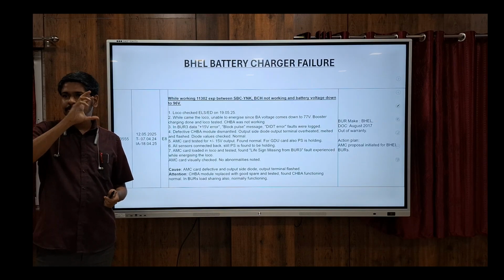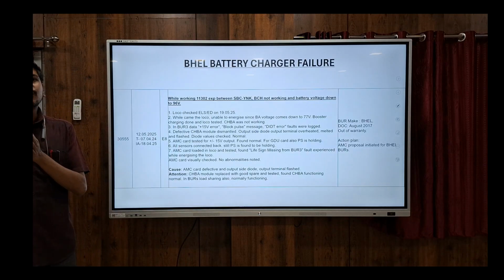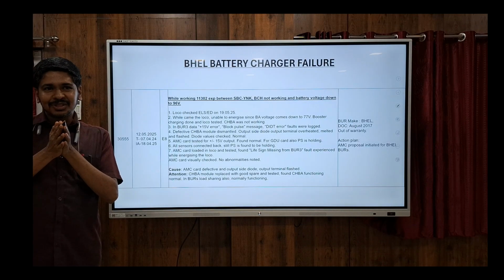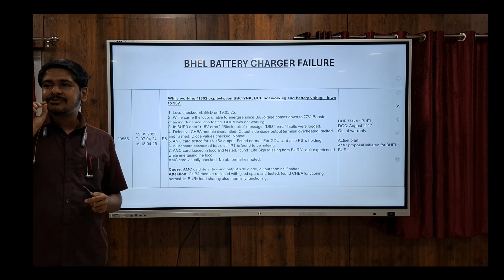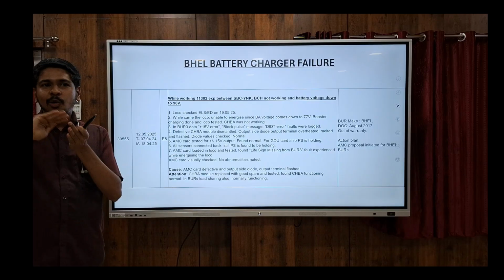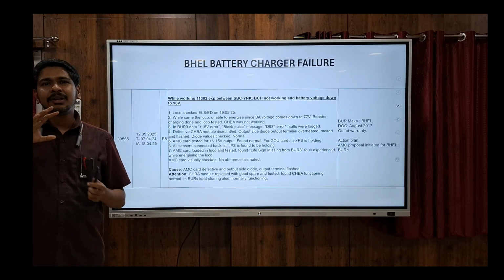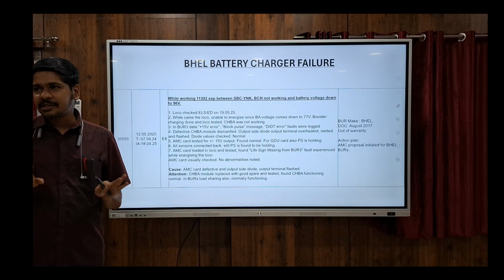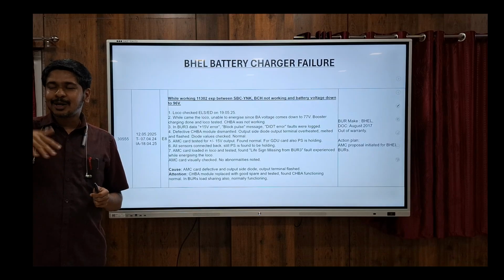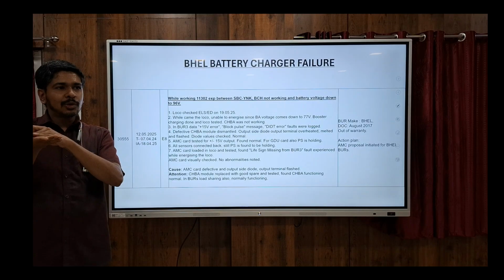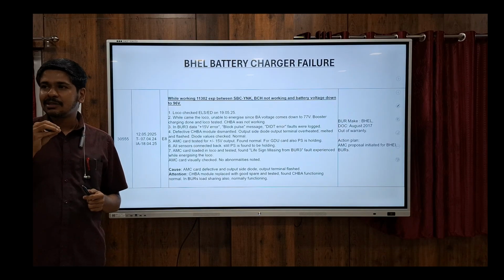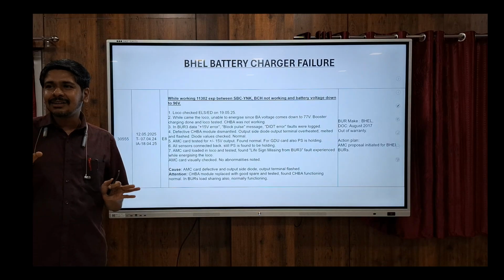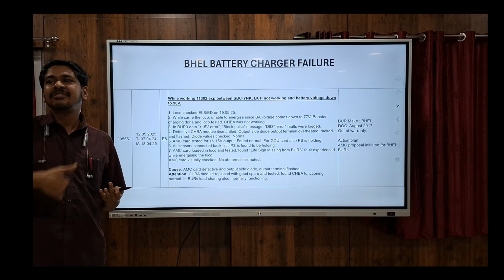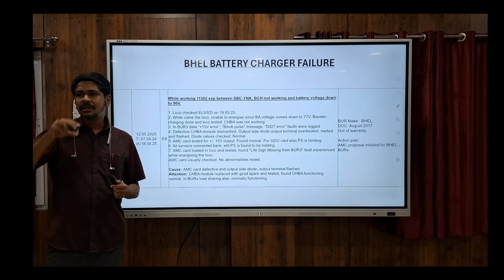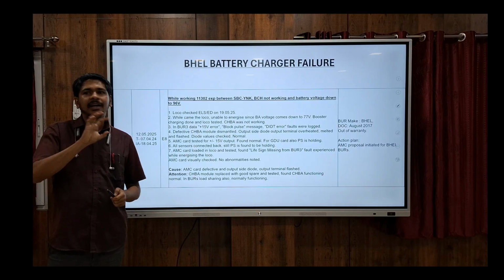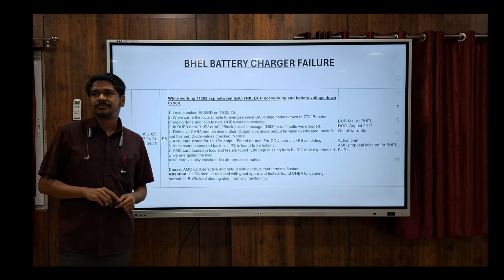Similarly, our battery charger control is also controlled by some cards which are driven by some power supply cards. If that plus or minus 15 volt has some fluctuation, the codes which have been driven to the battery charger control card cannot be properly executed, and it will make the battery charger surely fail. In addition to this, one more thing happened - near the module bottom side diode, some flash marks were also available. Since 2017 we have not opened this module, and after failure, when we opened the module, then only we got the flash marks, and the bolts which are tightening the diode were also in a molten condition at that time.